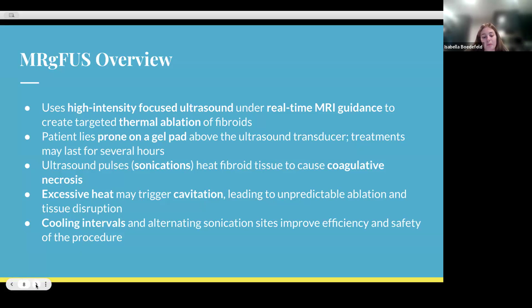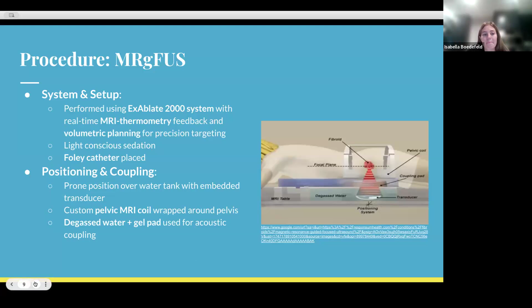And so in this study, the Exablate 2000 system was used with real-time MRI thermometry feedback and volumetric planning for precision targeting. Patients received light conscious sedation, had a Foley catheter placed, and were positioned prone over the water tank with a transducer embedded in the table. And I kind of put a picture of what that would look like off to the side. And a custom pelvic MRI coil was used for imaging, and degassed water plus a gel pad provided acoustic coupling between the patient and the ultrasound beam.